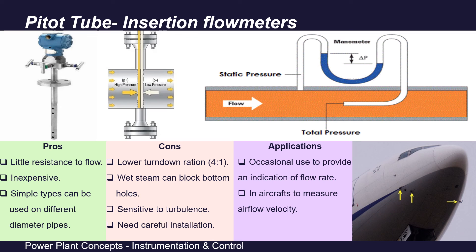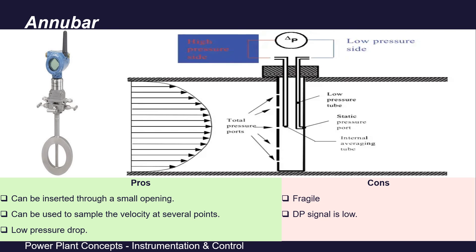Annubars are insertion-type devices that can be inserted through small openings, can sample velocity at several points, and have low pressure drop with minimal obstruction. Disadvantages include that they provide only single-point measurement, the pitot tube element is fragile, and the differential pressure signal is low — a weak signal.